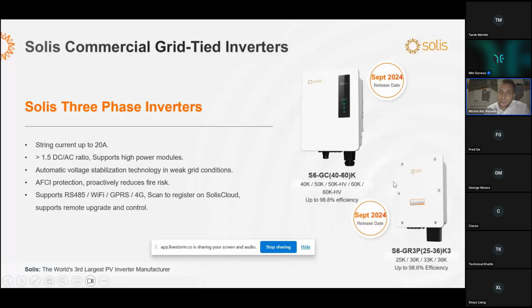For the higher range, which is now small capacity C&I, between 25 and 60 kilowatt, the string current is up to 20 amp, with a 1.5 DC to AC ratio. With a 20 amp string current, we are talking about 40 amp per MPPT. So they are compatible with all new PV modules being introduced in the market, high current, low voltage. They are also equipped with AFCI protection and support communication through RS485, Wi-Fi, GPRS, and 4G, can be accessed through our cloud, and support remote upgrade and control.